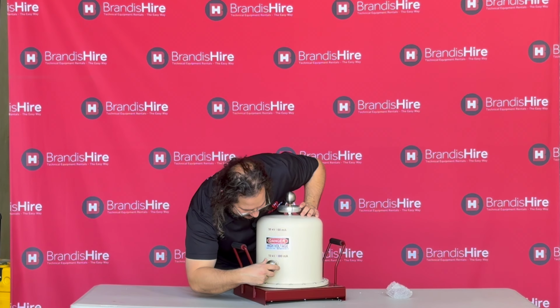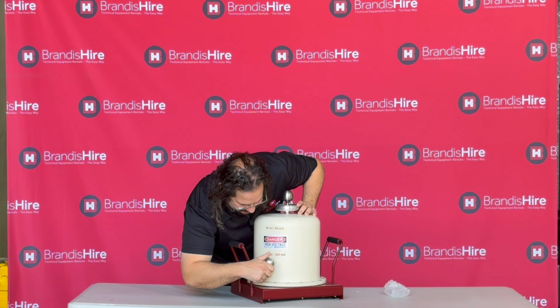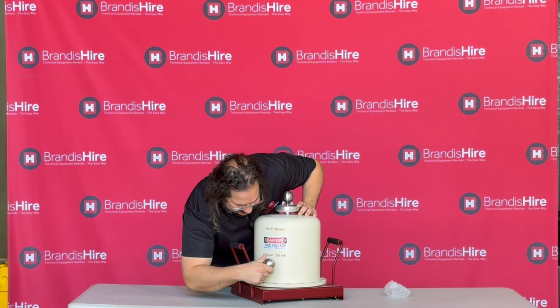Now, one thing to note is these balls. So these nice round spherical balls give you a perfect distribution of electrical flux. That's really important for when you're doing PD testing. Why is that important? Because it means that you get a nice low level of background PD, which matches the PD output of this transformer, because this is designed for PD testing. This has less than 3 pico of partial discharge all the way up to 50 kV.